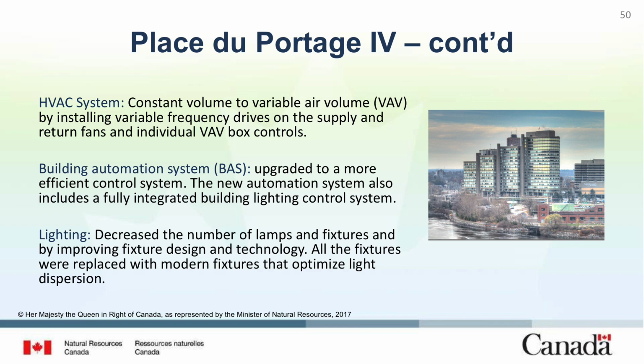For example, corridor spaces had ample light fixtures, but the light distribution was uneven, and much of the corridor space was not well lit. All the fixtures were replaced with modern fixtures that optimized light dispersion. This measure decreased the number of light fixtures while simultaneously providing improved, uniform lighting levels throughout these areas. These upgrades and the flexibility of the EPC financing option allowed the Place du Portage building to see significant energy savings, optimized building operation, and improved occupant satisfaction.